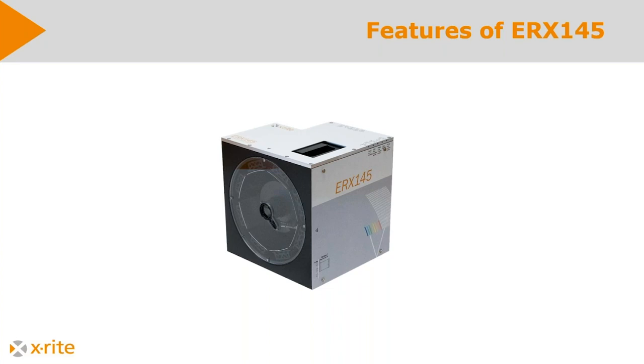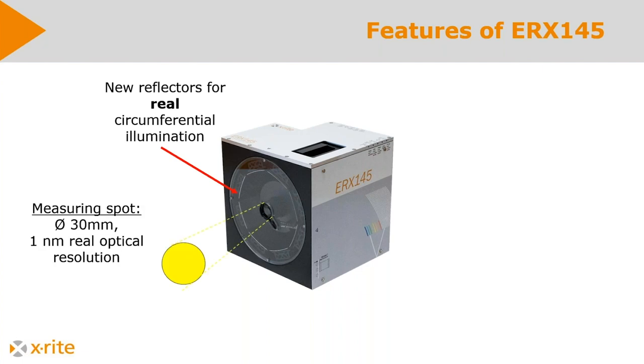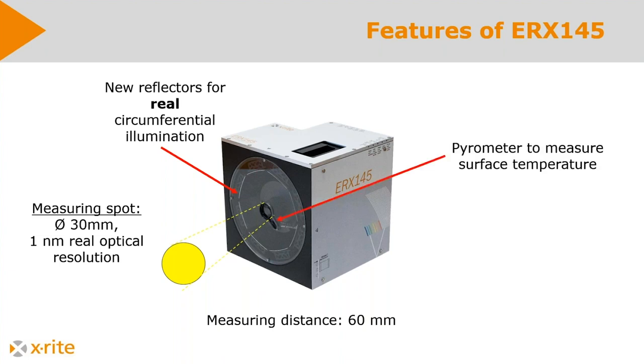Okay, this is how the head looks. In front there is a ring mirror inside which is illuminating under 45 degrees. We have a spot measurement of 30 millimeters, and I said already the 1 nanometer optical resolution. We have a measurement distance of 60 millimeters, which gives a nice clearance between the web and the instrument. We have a pyrometer over there to measure the surface temperature, and I will show you later why this is necessary. Everything is protected by a glass pane against dust.